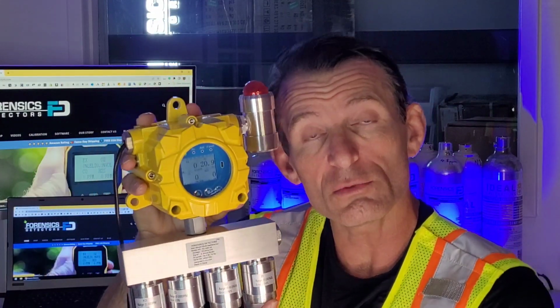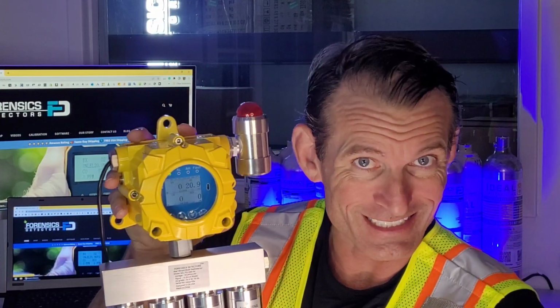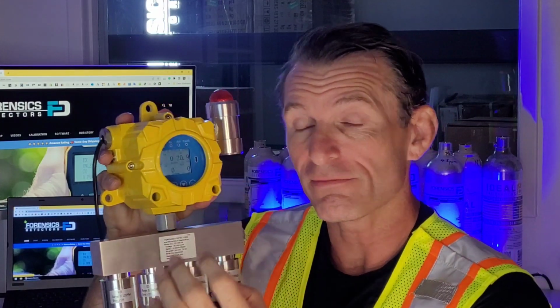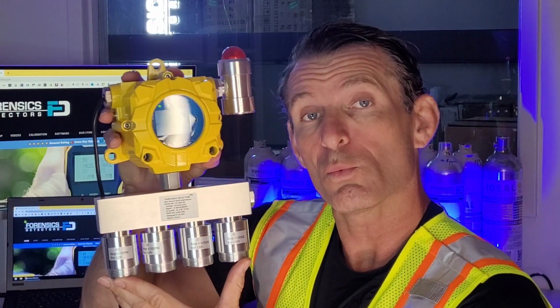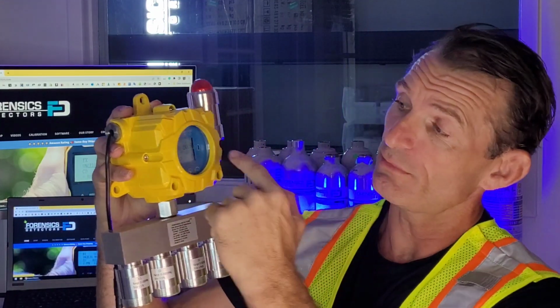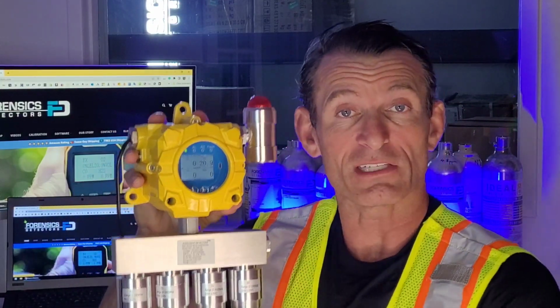So this is good for those situations where you have a little cabin or a little closet or a room, it's confined, so the entry and exit is limited, and you want to continuously monitor the gases, the safety of that environment. We do that with this guy, so that would prevent anyone from having to do a sample before entering. One could just look from a distance and make sure it's not alarming, which then confirms the volume of space is safe to enter.